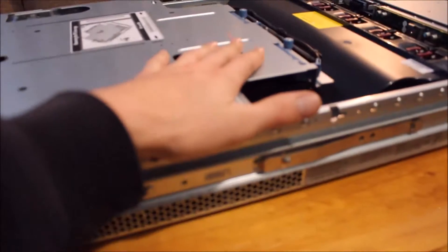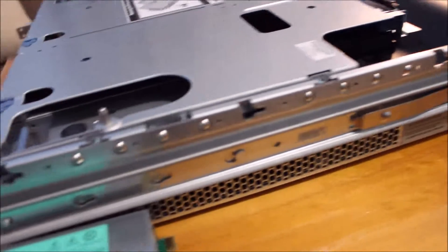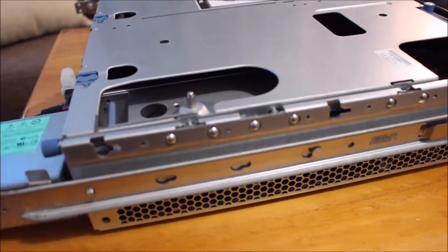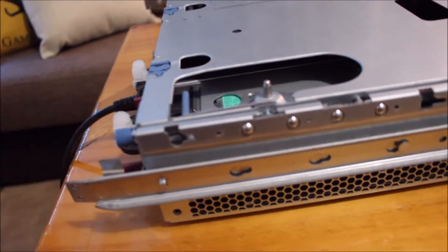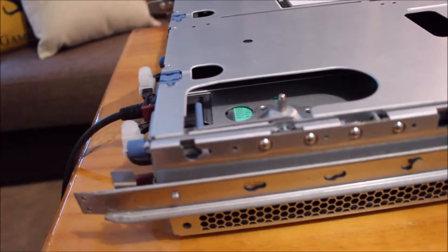In the actual server, it will have its own local voltage regulation for things like the CPUs — like any standard motherboard — and also extra regulation for 5 volts for the hard drives. These power supplies are hot-swappable. Red tags mean hot-swappable. Blue means don't touch it when it's running.